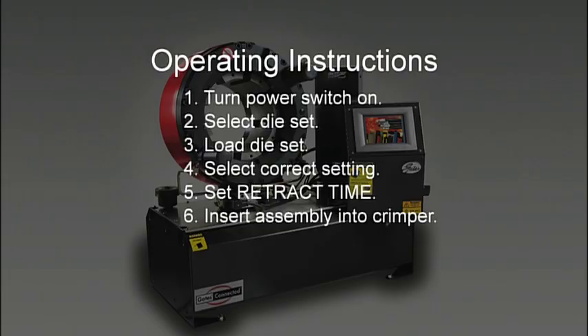6. Insert the assembly into the crimper head. Insert straight assemblies through either the front or the back of the crimper head. If a bent tube is being crimped, it must be crimped by loading the assembly from the rear of the crimper. Jog the crimp dies until they just contact the ferrule. Be sure the ferrule and crimp dies are lined up properly to achieve proper crimp length. 7. Begin the crimp.